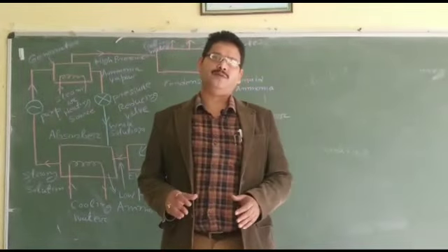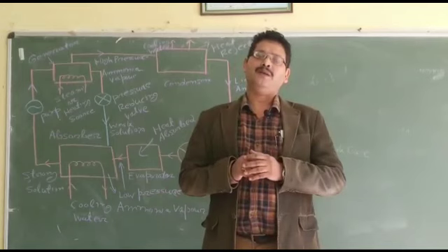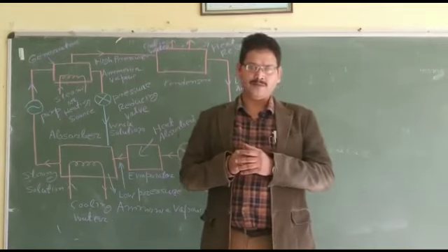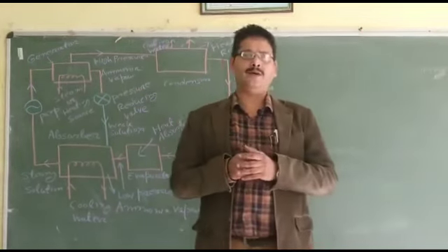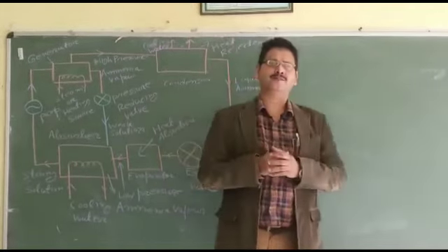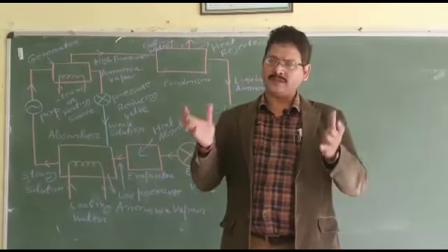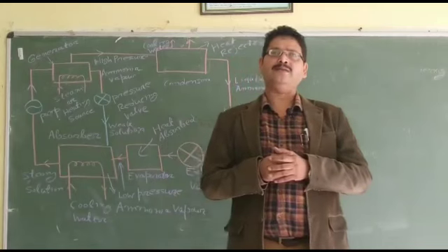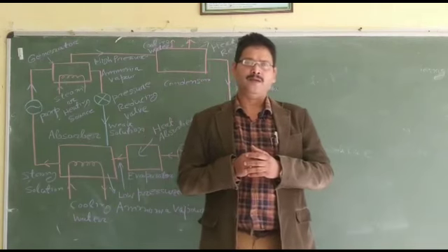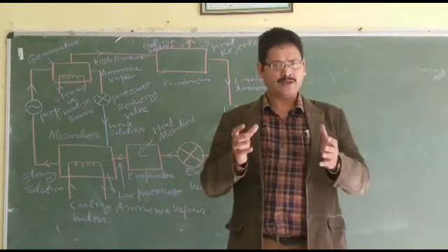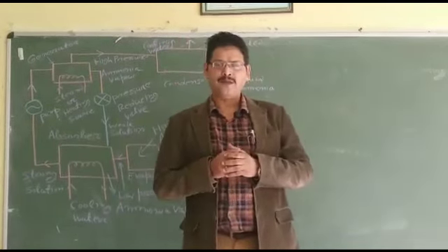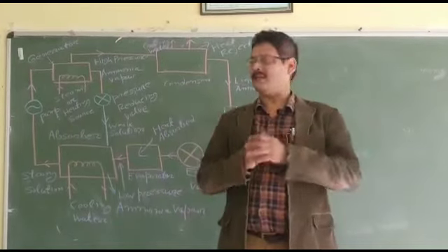So today we will discuss the simple vapor absorption refrigeration system. This simple vapor absorption refrigeration system was a widely used refrigeration system before the introduction of the mechanical refrigeration system. And the fundamental difference between the mechanical refrigeration system, which is basically your vapor compression refrigeration system, and the vapor absorption refrigeration system is that in case of your vapor absorption refrigeration system, the energy input that is given is heat or thermal energy, whereas in case of your vapor compression refrigeration system, the energy input is the mechanical energy.